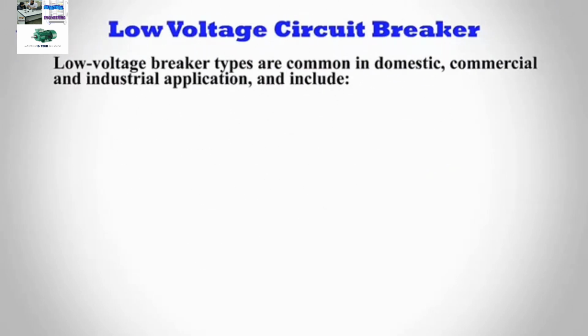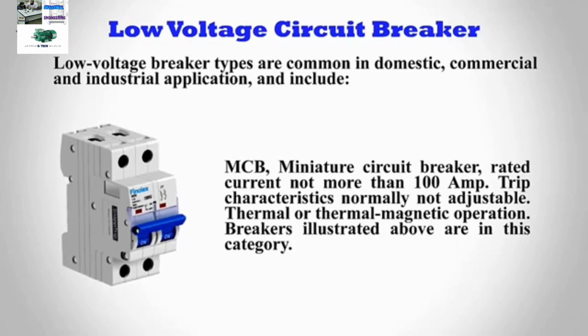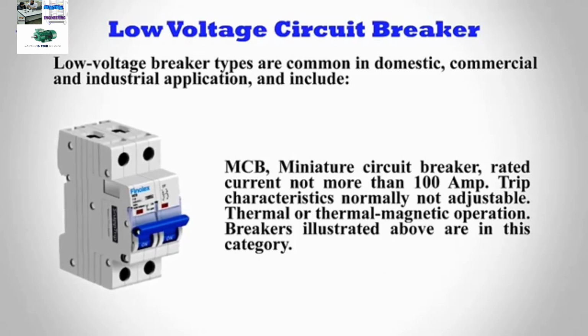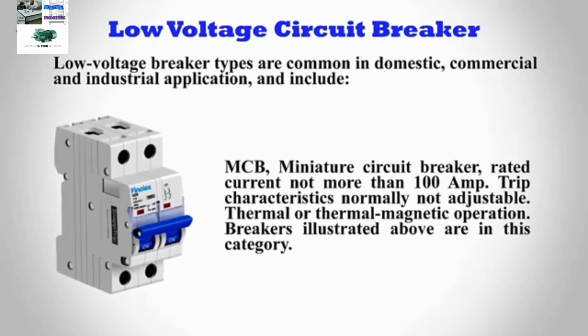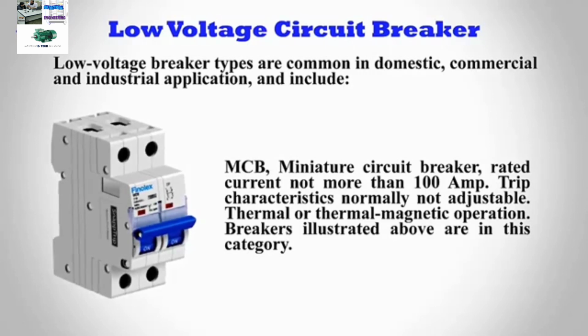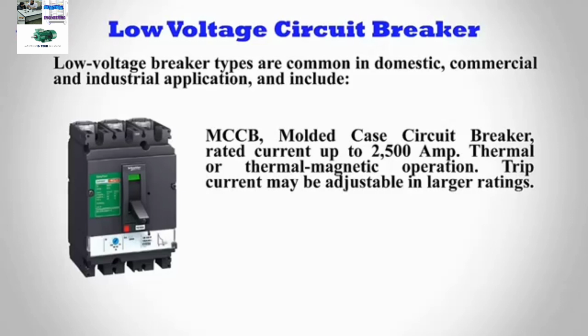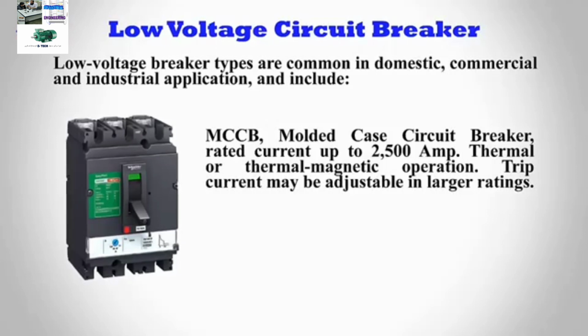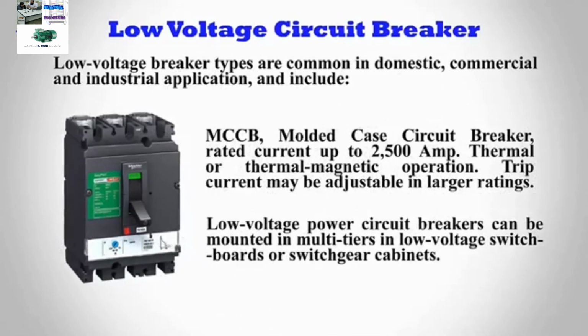Low voltage circuit breaker types are common in domestic, commercial, and industrial applications and include MCB, miniature circuit breaker, rated current not more than 100 amp. Trip characteristics are normally not adjustable. Thermal or thermal magnetic operation breakers illustrated above are in this category. MCCB, molded case circuit breaker, rated current up to 2500 amp, thermal or thermal magnetic operation. Trip current may be adjustable in larger ratings. Low voltage power circuit breakers can be mounted in multi-tiers in low voltage switchboards or switchgear cabinets.